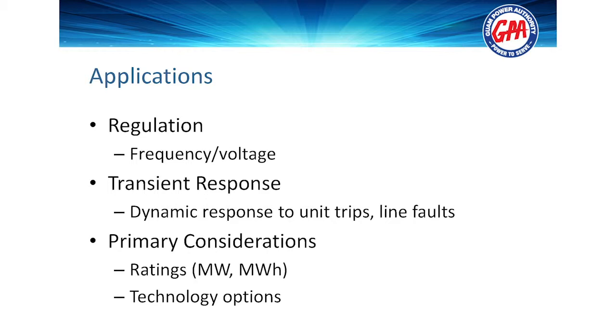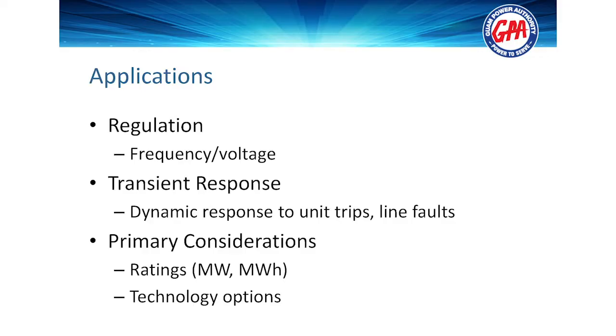As you add renewable generation, in a system like the GPA system, they may have had a load growth in the order of maybe a couple of megawatts a minute at their maximum load growth. That may be 3 or 4 times that when they start adding renewables. And how they deal with that is a huge issue. And so regulation, that's what's called regulation, is how you deal with the changes in your load. The transient response, this is one that is a very big problem in the Hawaiian Islands. It is a problem that you need to be able to deal with proactively.